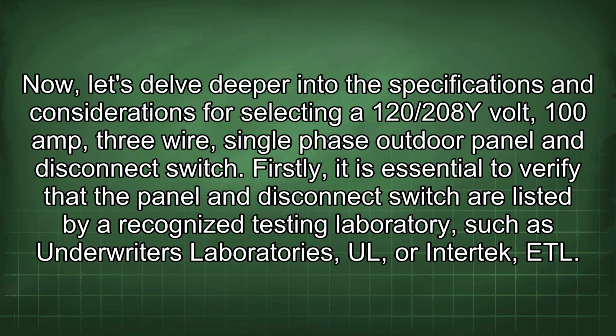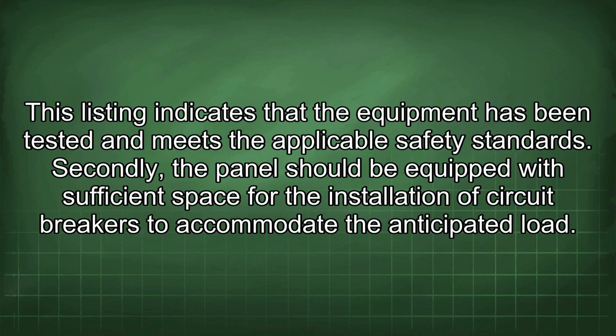Now, let's delve deeper into the specifications and considerations for selecting a 120/208 volt, 100 amp, 3-wire, single-phase outdoor panel and disconnect switch. Firstly, it is essential to verify that the panel and disconnect switch are listed by a recognized testing laboratory, such as Underwriters Laboratories, UL, or Intertek, ETL. This listing indicates that the equipment has been tested and meets the applicable safety standards.